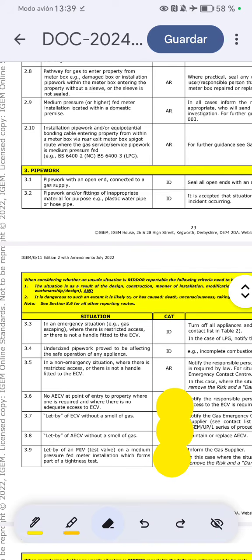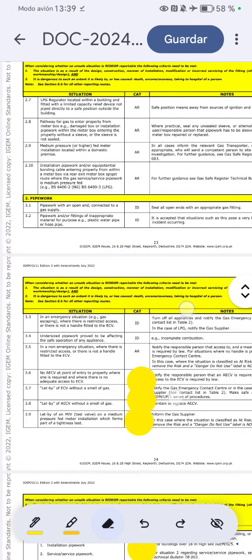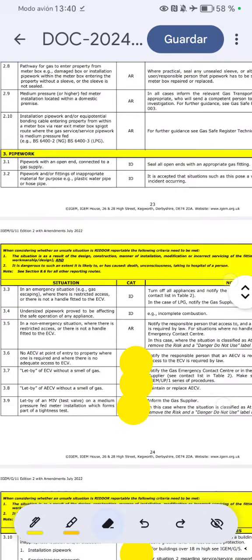I had this situation the other day and I didn't ID it. I didn't cap anything. I just wrote up a warning notice. I think it was an additional ECV. It wasn't the actual one at the meter, but nonetheless, I still booked it up. So there's a bit of information there. So I've got my first one wrong. I had a feeling it was at risk. Why was that? I think it's because I was on an ID roll and I just kept going.